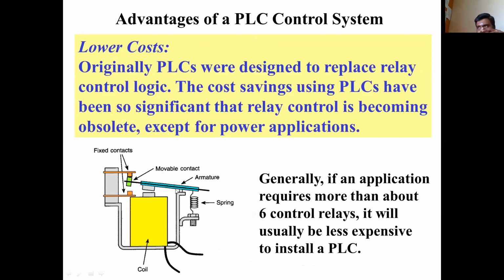Okay. So even though we are saying that the PLC is replacing the relay logic circuit, the output of the PLC will be connected to the relays. What is the PLC output? The PLC output gives only logic high or logic low. Logic high means it's giving 24 volt. Logic low means it gives 0 volt. So either it is 24 volt or 0 volt. Why 24 volt? Because the PLC is powered mostly by a 24 volt DC SMPS. So the output will be 24 volt DC.